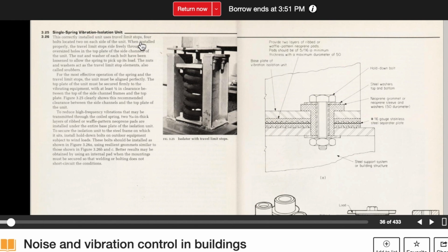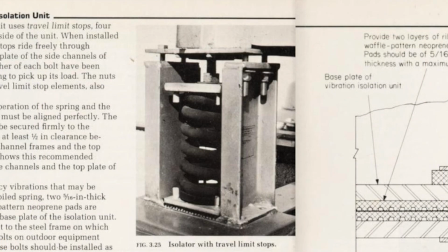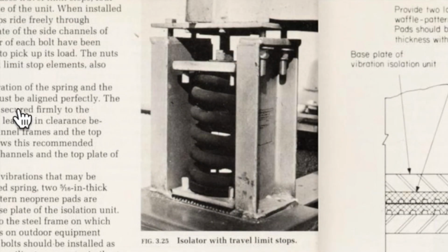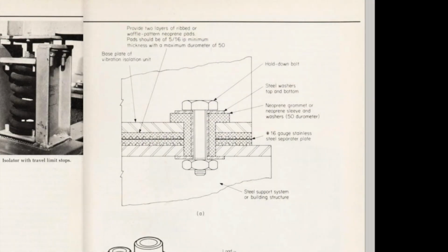Let's take a look at the level of detail this book goes into for specific issues. Here's an example of a single spring isolation unit that uses travel limit stops. So what's a travel limit stop? The top plate of the spring can move up and down, and it has bolts on either side, but there's a limit on how far the bolts can move. Also, to prevent vibration from transmitting through the coiled spring, you need to install neoprene pads under the base plate.